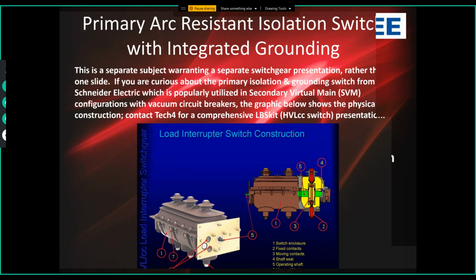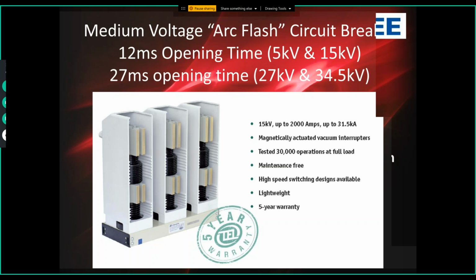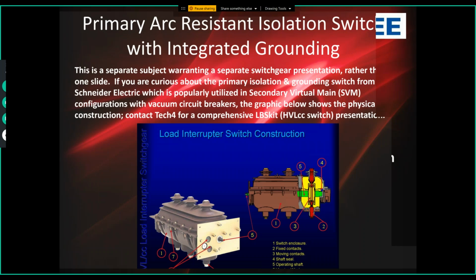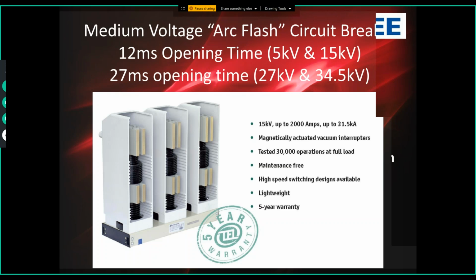So this switch in the one line is over this breaker, okay? So these are the two devices. Switch, you see the switch there, right? You see the slide? Yeah, yeah. Okay, that switch is only a matter of inches coming out the load side of that switch to the line side of this breaker. And this breaker can be in metal enclosed gear, fixed mount, or in metal clad gear, draw out. Either one. Now, when you put it in metal clad gear, since the switch is not withdrawable, that's really classified from the IEEE point of view as hybrid switchgear at that point.